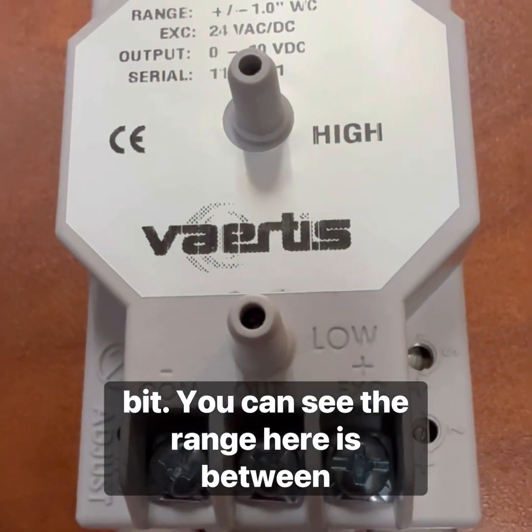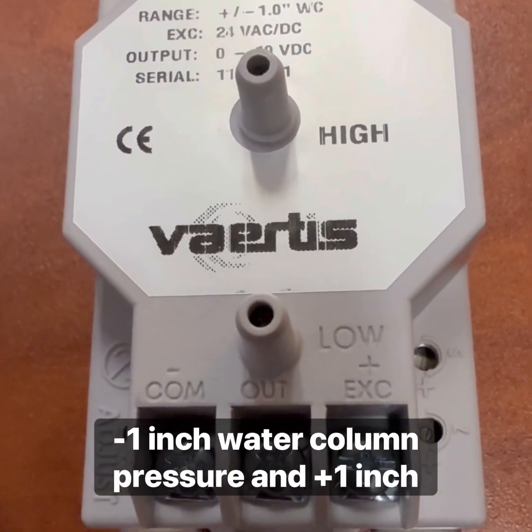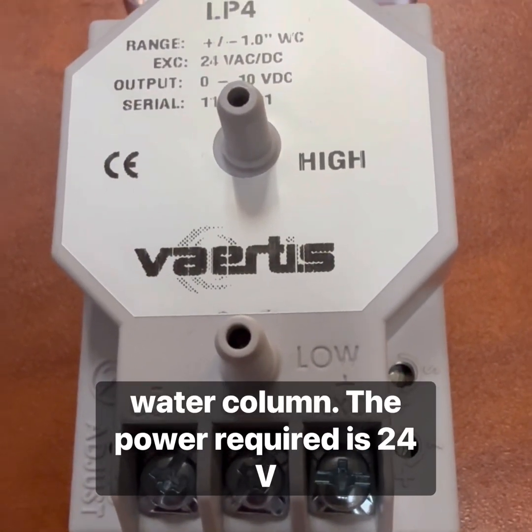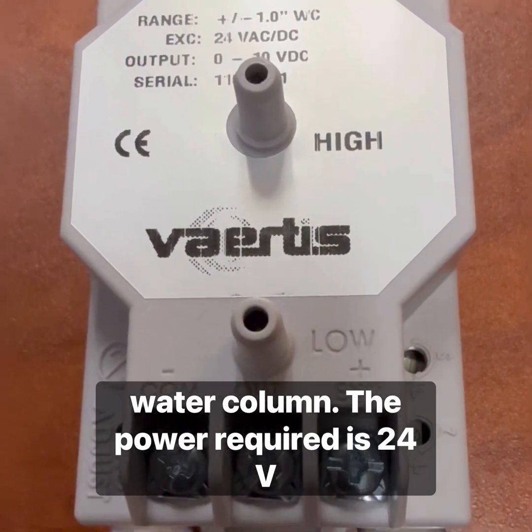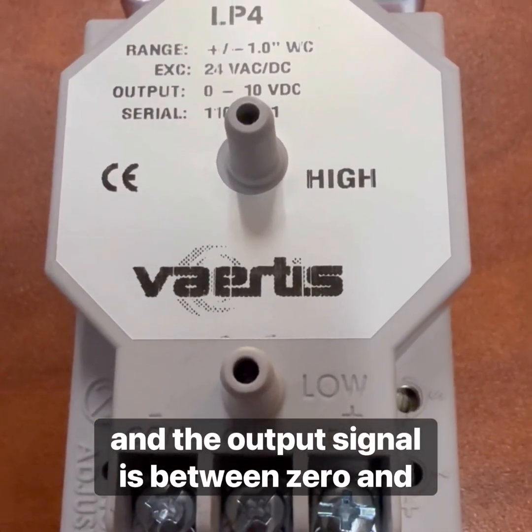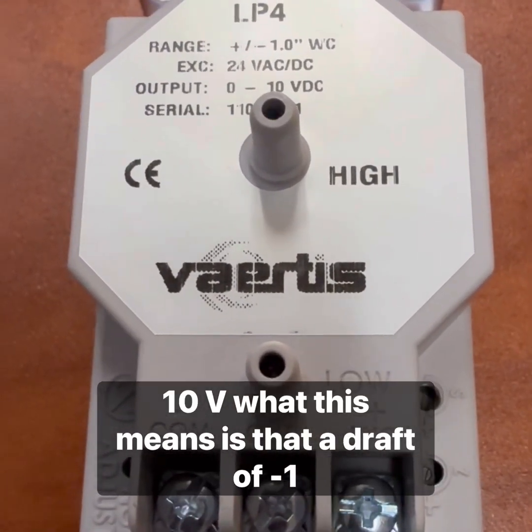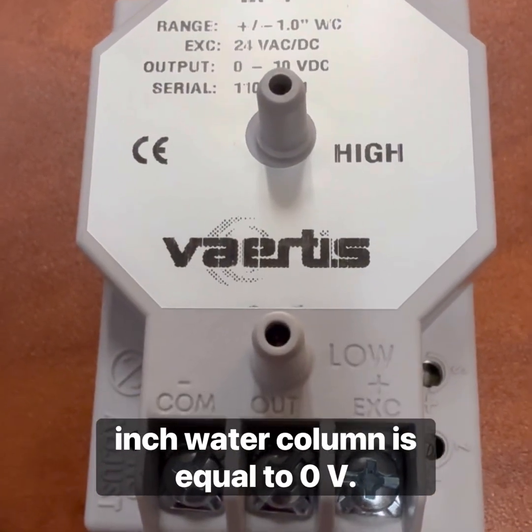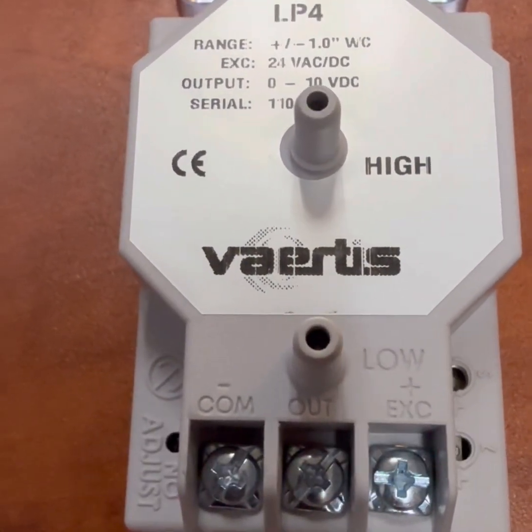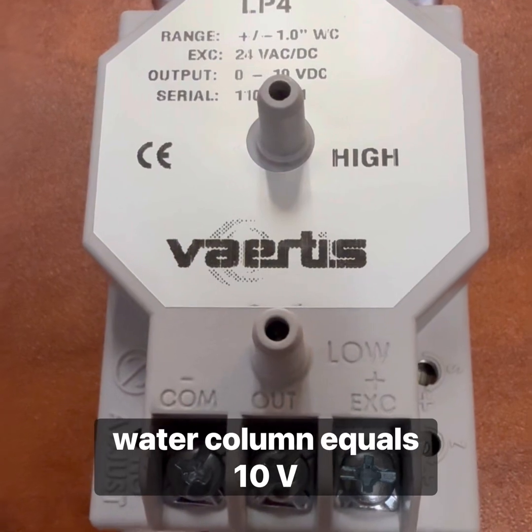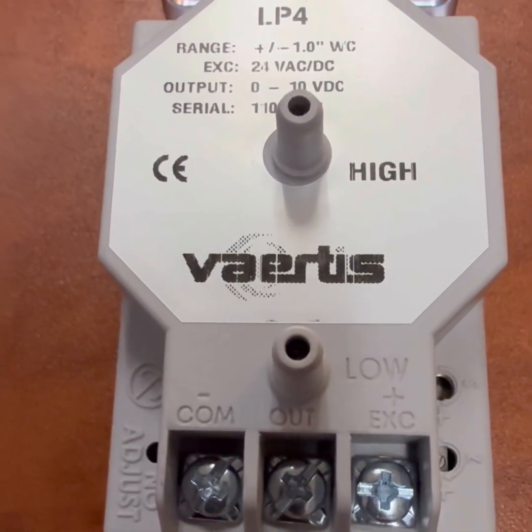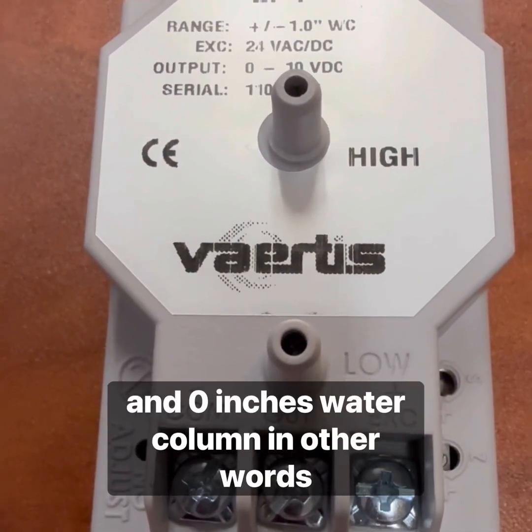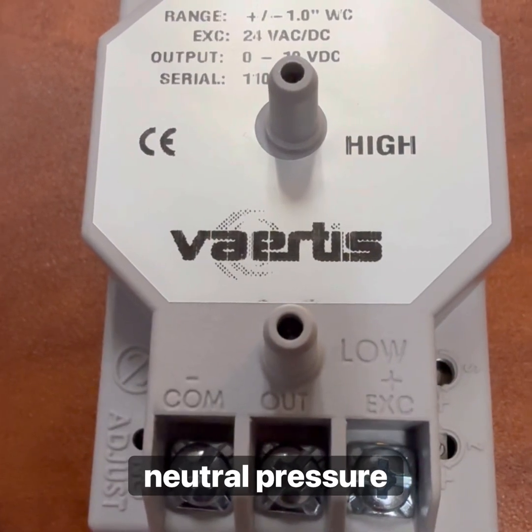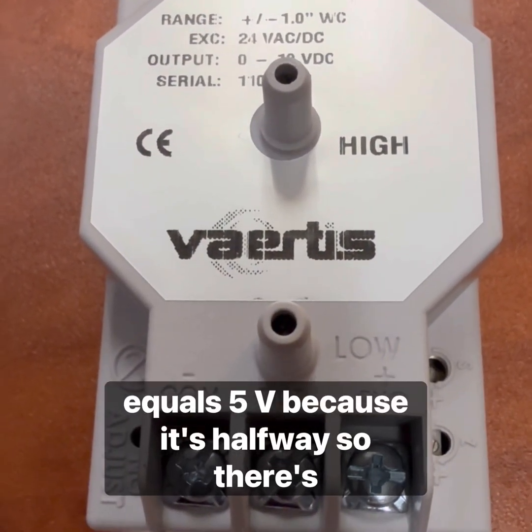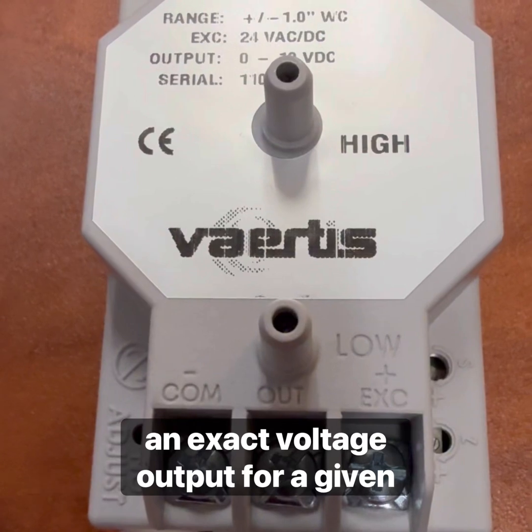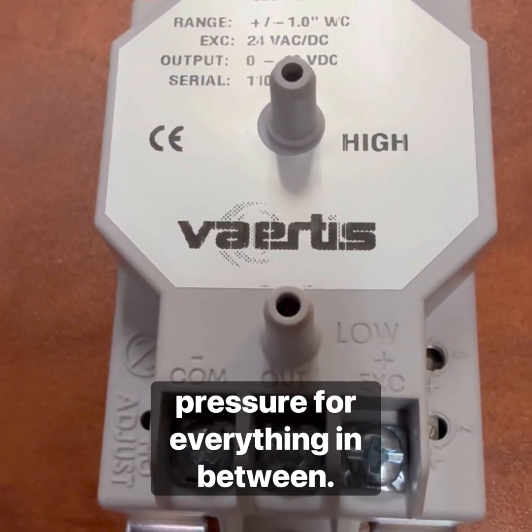You can see the range here is between negative 1-inch water column of pressure and positive 1-inch water column. The power required is 24 volts, and the output signal is between 0 and 10 volts. What this means is that a draft of negative 1-inch water column is equal to 0 volts, positive 1-inch water column equals 10 volts, and 0 inches of water column, in other words, neutral pressure, equals 5 volts because it's halfway. And so there's an exact voltage output for a given pressure for everything in between.